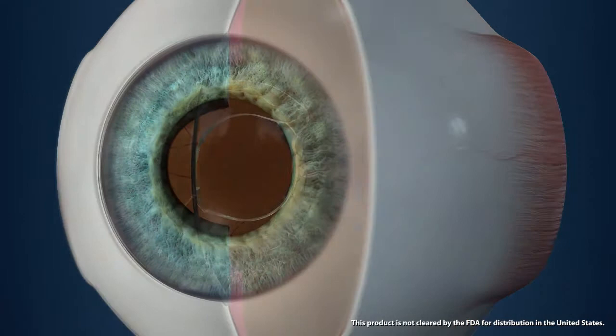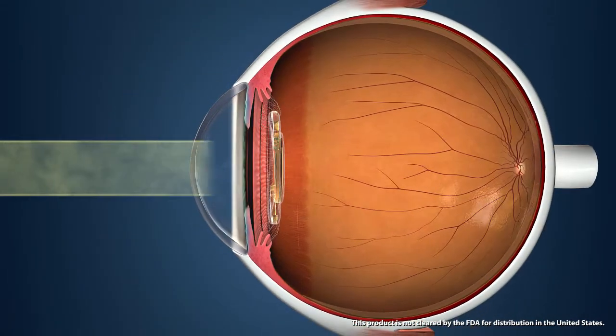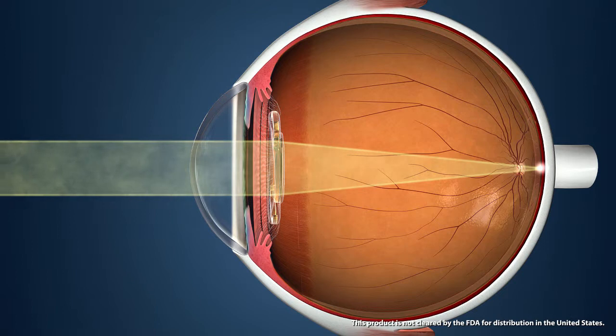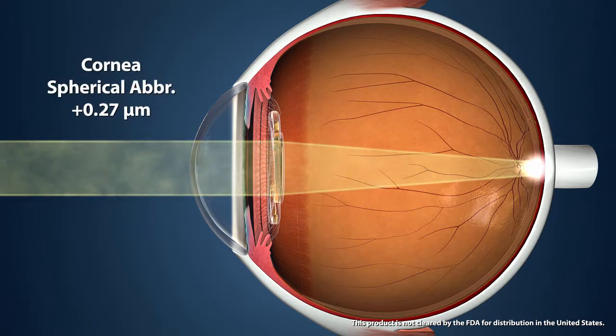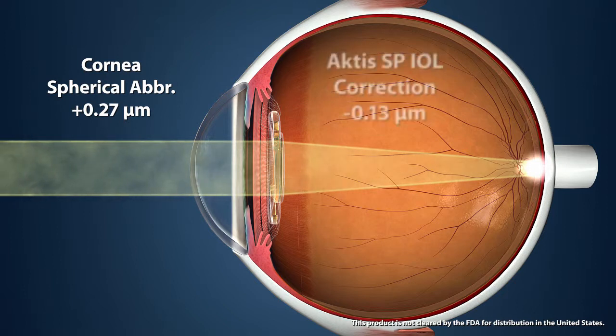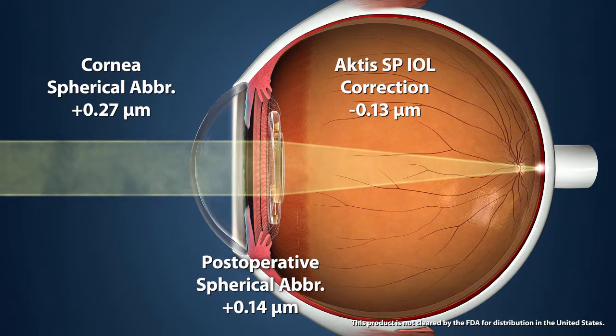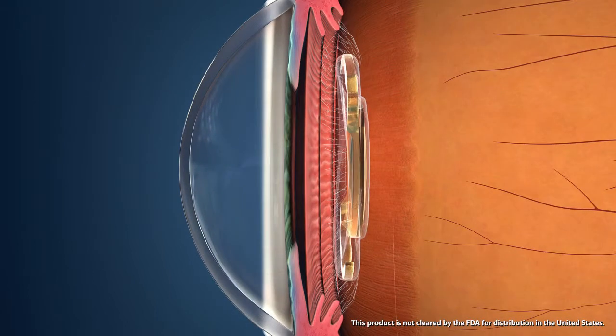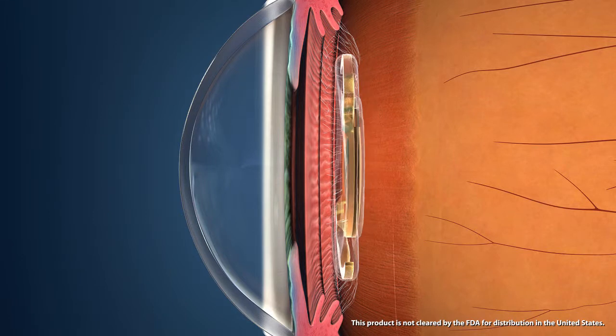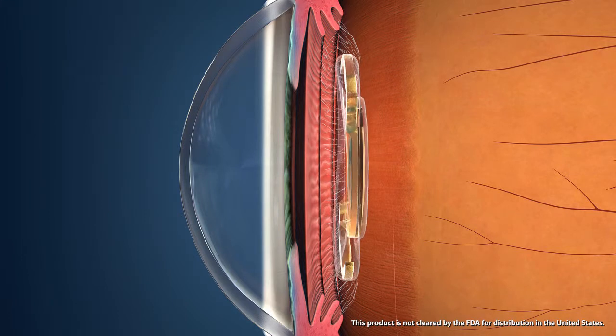The Aktis SP is an aspheric IOL designed to compensate for average corneal spherical aberration, which is positive 0.27 micrometers in a normal cornea. The Aktis SP corrects negative 0.13 micrometers, targeting a total postoperative spherical aberration of positive 0.14 micrometers, increasing depth of focus. This feature also helps to compensate for any IOL deviation within the capsule or bag.